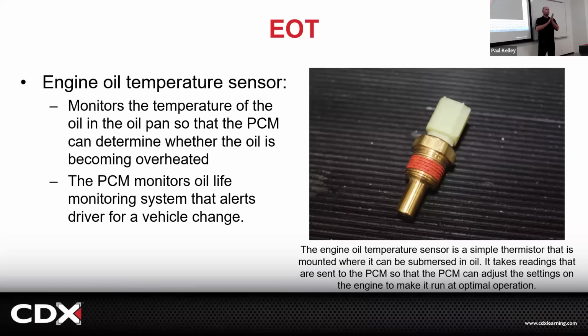You want to know the really cool thing? You diagnose them the same. All the temperature sensors are the same. We covered that a little bit in the electrical part, but the most simple way is measuring the resistance of the sensor at a specific temperature and checking it on a graph. So if it says at 68 degrees this temperature sensor should be 10,000 ohms, you're going to literally use the meter to measure: is it 10,000 ohms at 68 degrees? Yes or no? And if it's not, that'd be a fail.